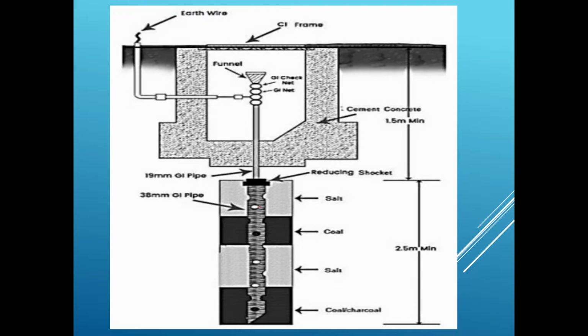The earthing wires are connected to the top section of the pipe, above the ground level, with nuts and bolts. The contact surface of this GI pipe with the soil is more compared to the plate type. Hence it can handle large leakage currents for the same electrode size. The earth wire connected above the ground level can be physically inspected from time to time.